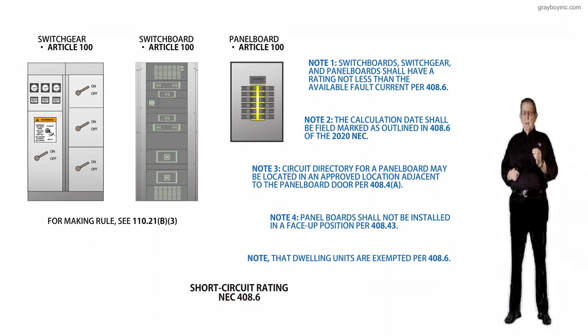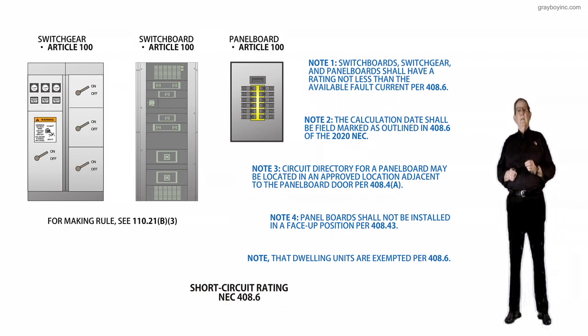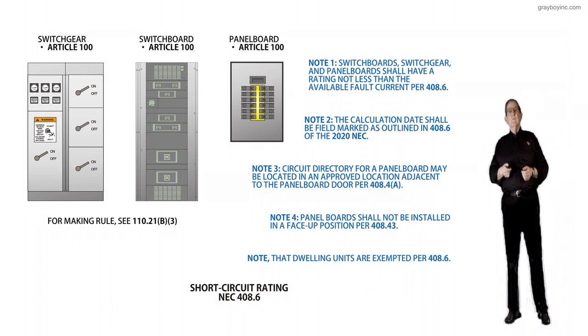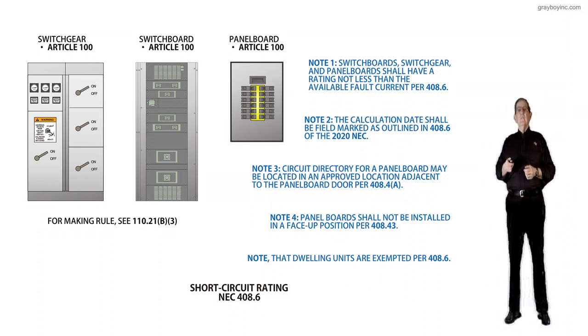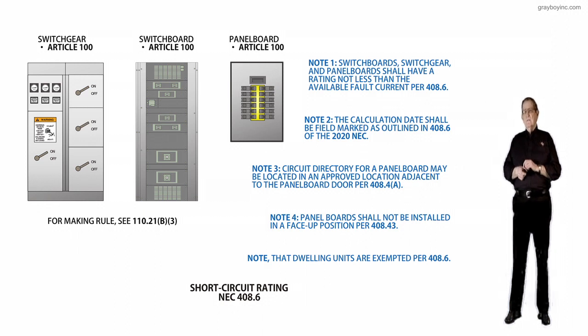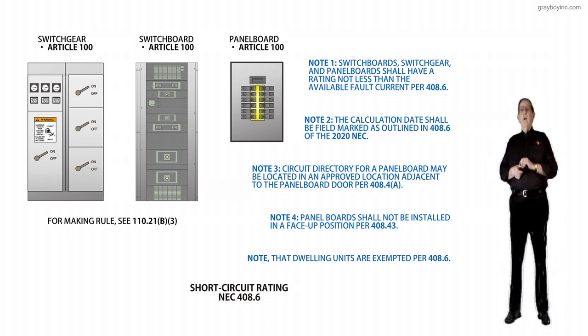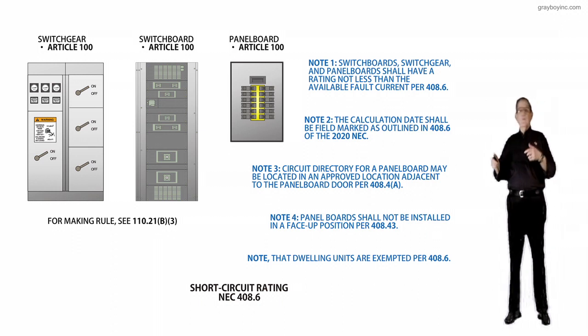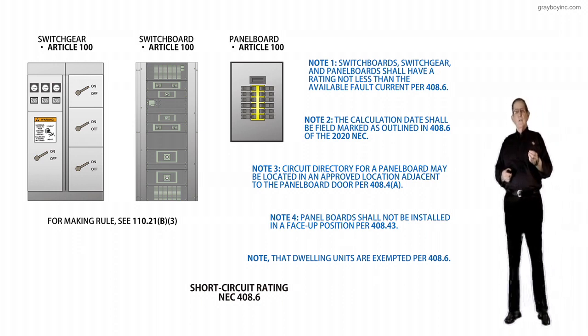Now, reviewing the electrical equipment, notice we have switchgear defined in Article 100. That's to the left. It racks items in and out. Then you have the switchboard, and you have these stationary protective devices there. And then you have your panel board, and those devices are permanently installed, and they're not adjustable in any way. They're either 15, 20, 30, et cetera, in accordance with Table 240.6(A).